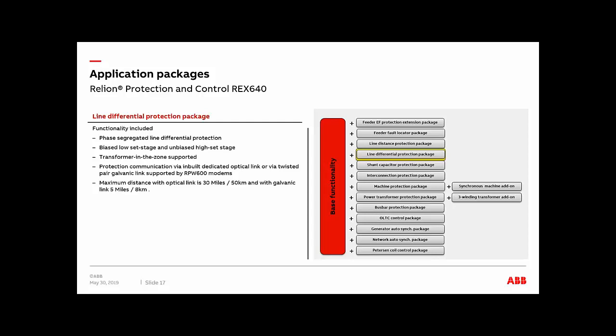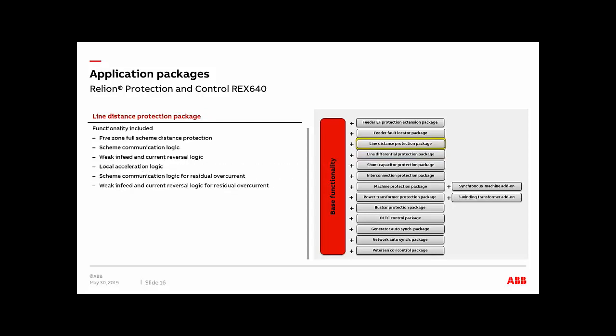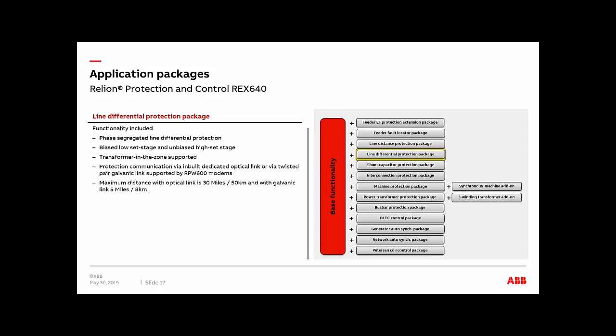Now on the line differential package, let me just for a second go back really quick here to our line distance. It's good to mention here that we do have protection communication enabling the possibility to transfer up to 16 additional binary signals between line ends at a maximum of 30-mile distance. This is a dedicated communication channel that the relay has, which is going to be in place as well here for the line differential, where we're going to have a phase segregated line differential protection. We're going to have 3 configurable slopes and a high stage instantaneous trip.